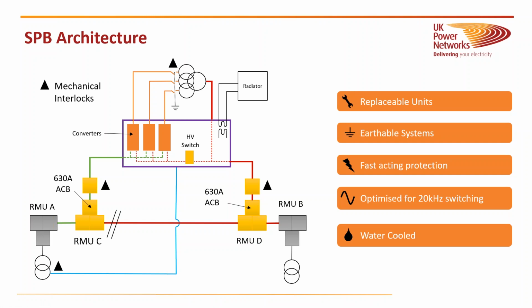Obviously, because of this, the converters being at 1 MVA, you're limited in operation by the voltage difference between the feeders. Because of that, ideally you want to place them somewhere where you've got similar voltage either side, and then similar impedance. For that reason, we place them at secondary substations, and this being a first of its kind device means there are some quite tricky space constraints that we're having to deal with. But as I say, this is a first iteration of this device. When we're placing it here, there are quite a few important things to think about in this architecture and why we've created it like this. Mainly for safety reasons.